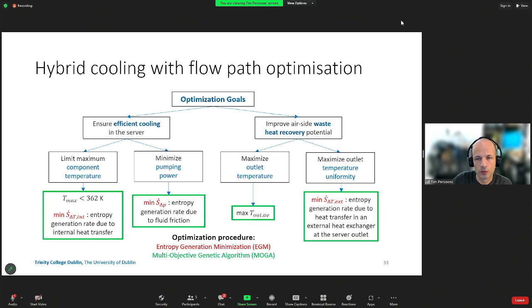So the optimization problem looks something like this. We want to both ensure efficient cooling of the system, as well as improve the waste heat recovery potential, right? So on the efficient cooling side, we obviously want to limit the maximum component temperature. So we have some limit there. We want to minimize pumping power. And so this combination here is what we were talking about earlier in the heatsink design. So the sum of these 2 components will lead to an optimum heatsink design in terms of efficient cooling.